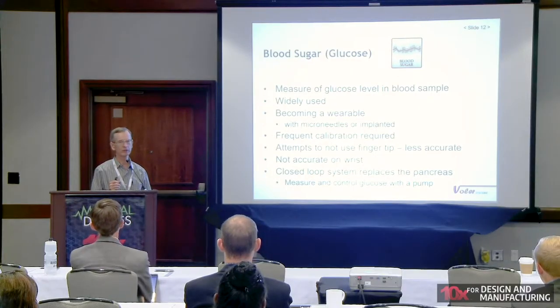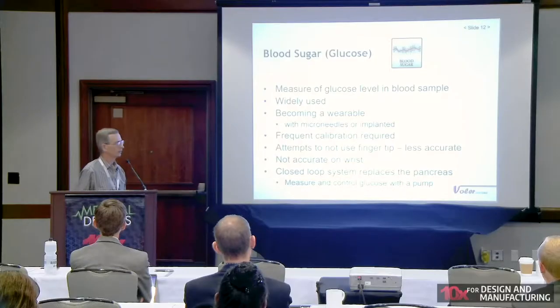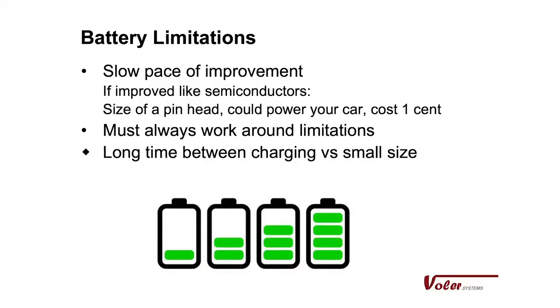Glucose measurement is another common one. Today we have wearable patches with micro needles — they don't feel like needles, they just go through the skin enough to pick up a glucose signal. They do require calibration; you have to prick your finger once or twice a day because they're not accurate over a long period of time. Also, you need very good blood perfusion where you're measuring, so the wrist is not a good place. The most common place people want a wearable device — the wrist — is probably the worst place to put it. We now have sensors combined with insulin pumps, making a wearable pancreas even for type 1 diabetes.